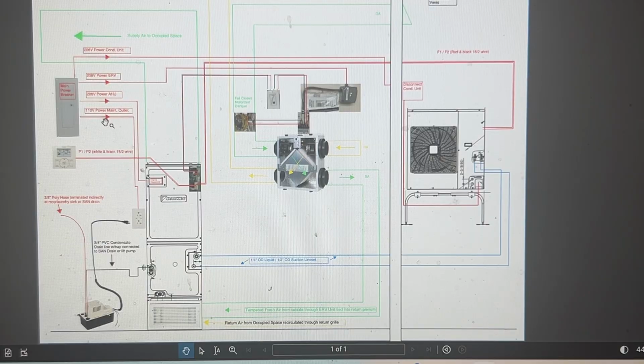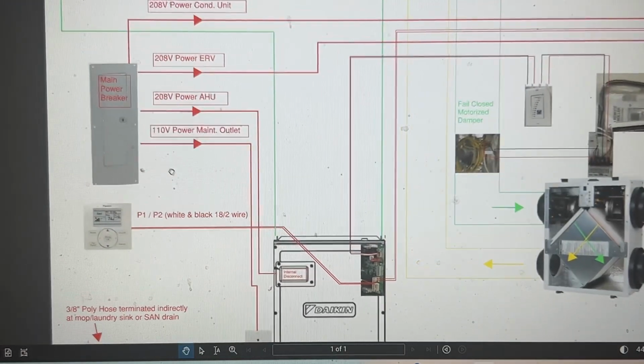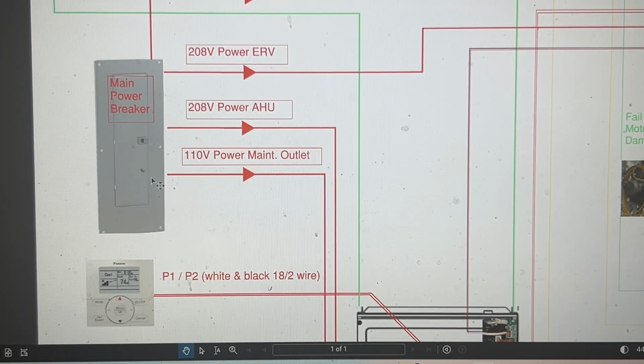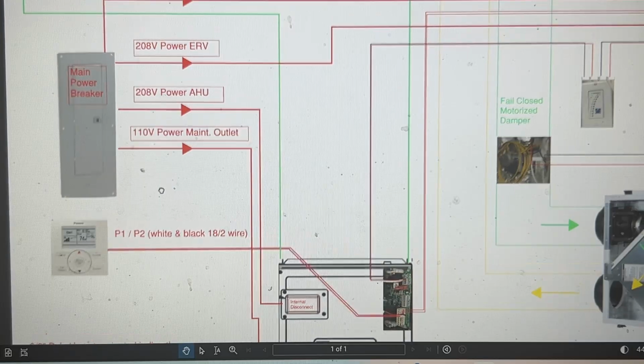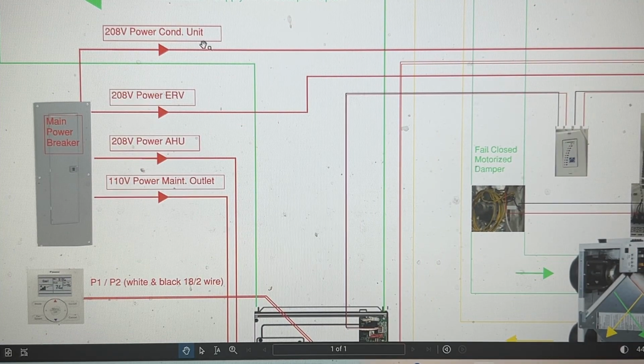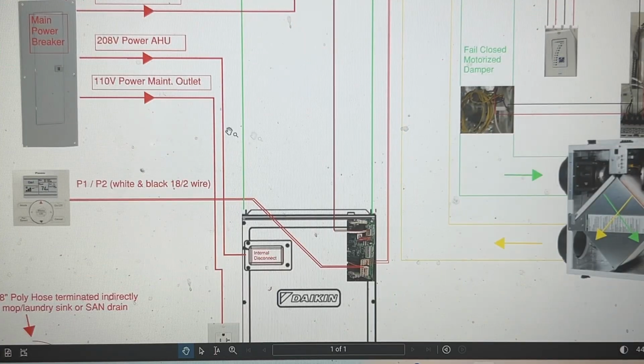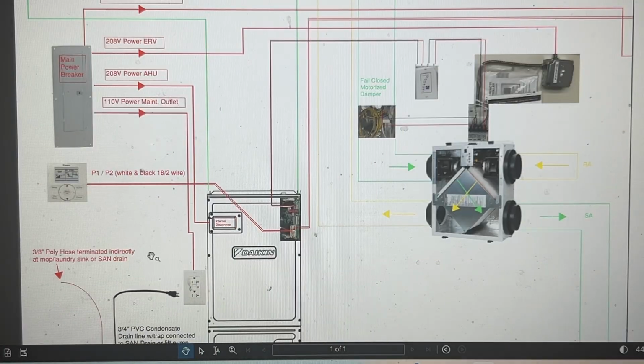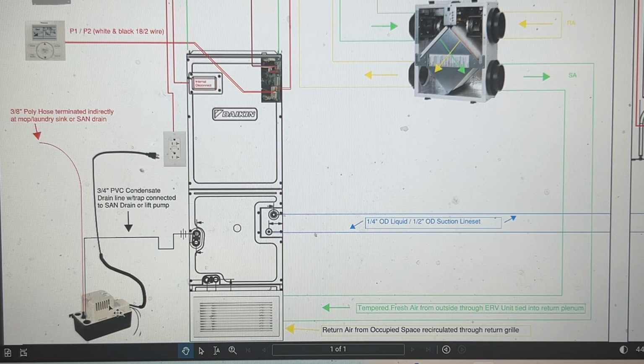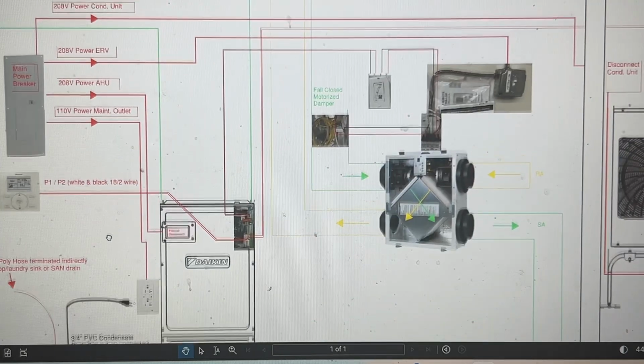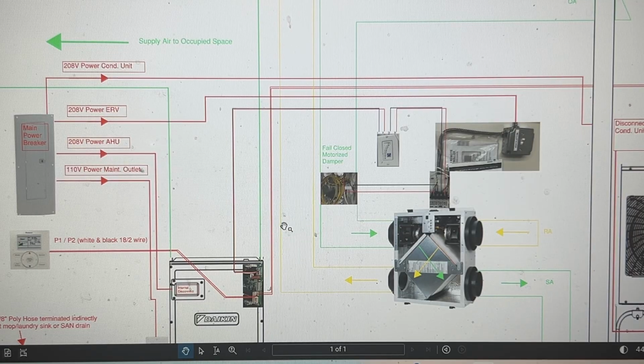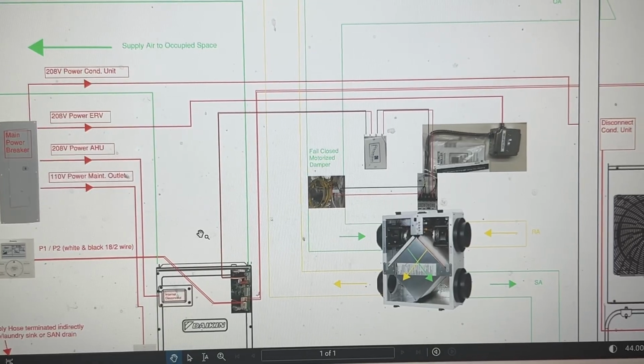All right, so power wiring. This would be just like we all have at home, our main power breaker panel. What we needed for power was 208 to the outside unit, independent. So there'll be a breaker in here with a power feed to the outside condensing unit. There'll be another breaker for the ERV unit, another breaker for the indoor air handling unit, and then a 110 volt service outlet right at the indoor unit as well. That will be the power supply for our condensate pump. So there are 4 breakers specific that we need to serve power to make this system work properly.